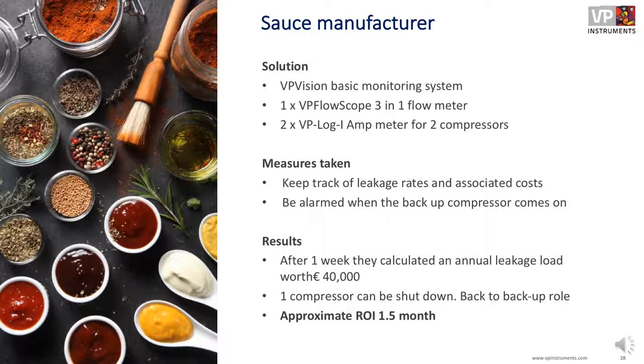Now the sauce manufacturer, which has a much smaller footprint in terms of energy used to run its processes, was a lot smaller company with just one compressor location. But just by putting in a basic monitoring system, one flow meter, and two amp meters, we were able to detect the behavior and the on and off cycles of the compressors and how much air was being delivered by them.